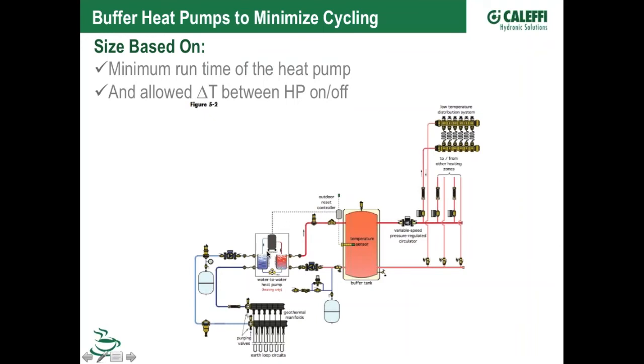So Thermocon can be used for chilled water. It's insulated all around. It's a foam-lined tank, so this could hold heated or chilled water, and we're just going to pipe right into that. We're going to put our air elimination device there. We've got the well in the center for the temperature probe, so you might drive this heat pump right from a temperature sensor well in the center of the tank. Air elimination at the top, a drain valve at the bottom.